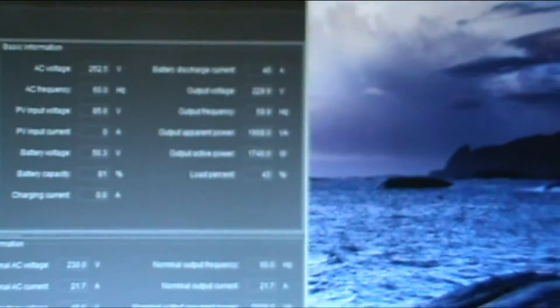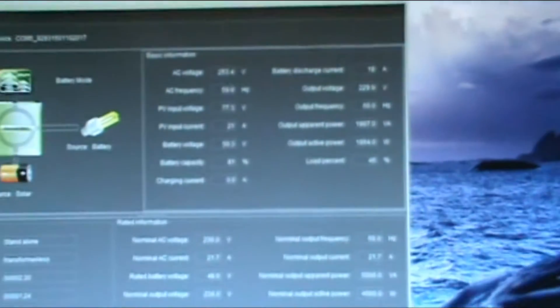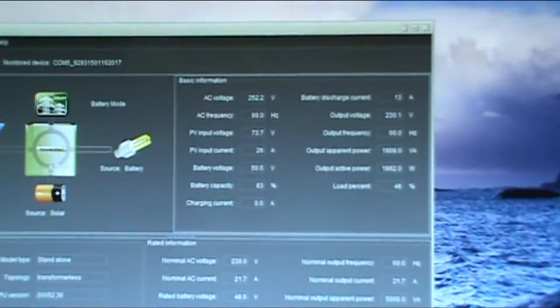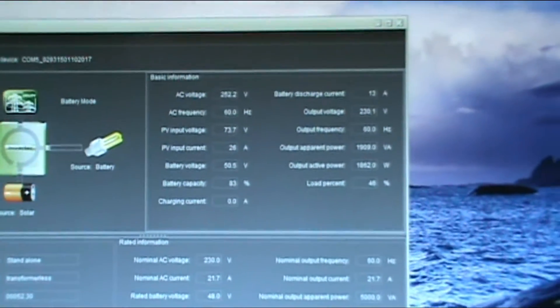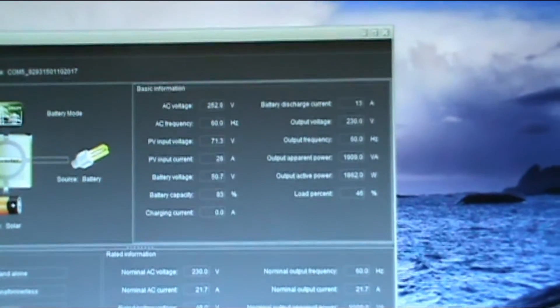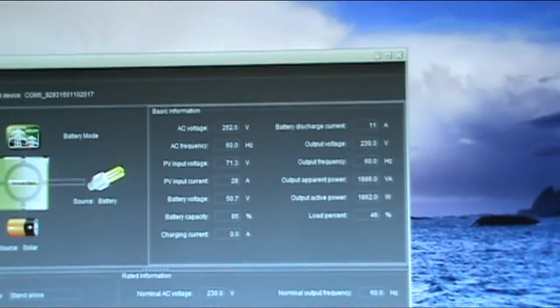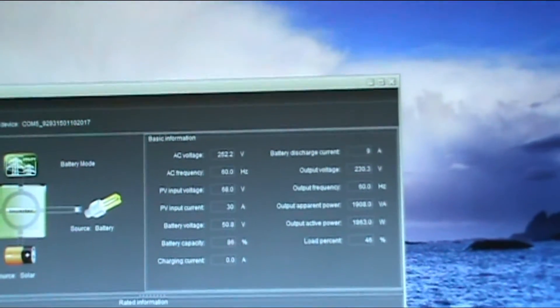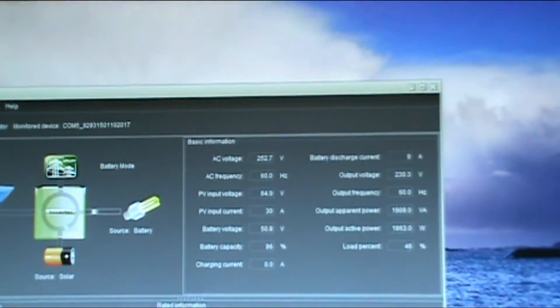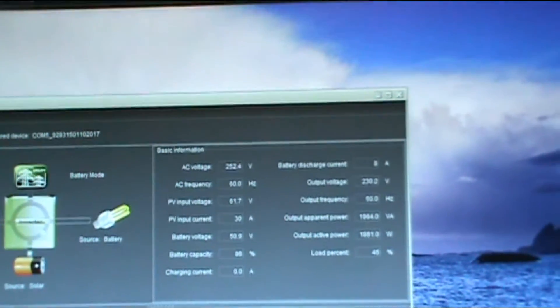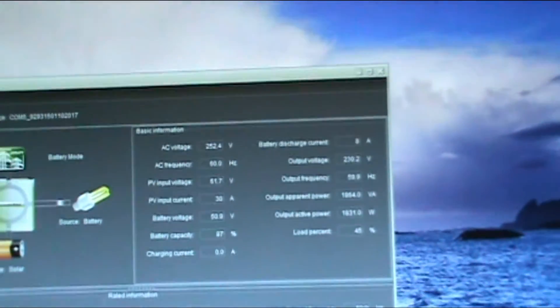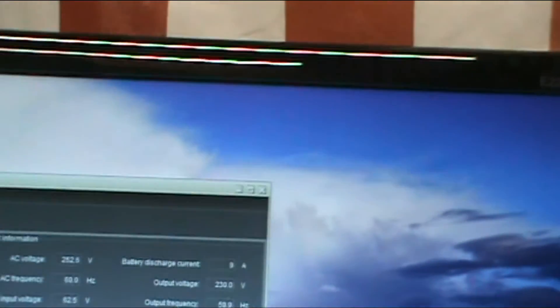Right now the Victron's saying I'm pulling a negative two kilowatts out of the battery bank, but once the solar - there they are, the relay just clicked. Sooner or later this will change and we should start getting current going in. It takes a little while for the MPPT to lock on when it changes like this. There we go, MPPT locked back on. Drawing 26, 28 amps, 30 amps. That's what we're pulling out of the solar, right at 30 amps. I'm going to put on a little bit more load.